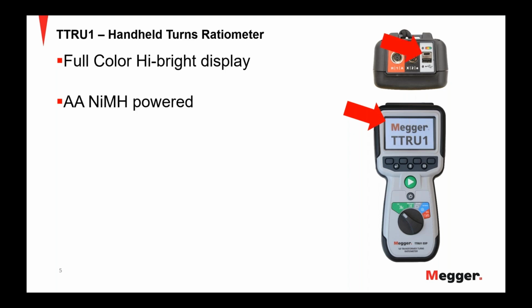It is a battery powered device, and AA batteries are nothing new, but what is new is the ability to charge the batteries using a USB-C cable. The USB-C cable is the same cable that you're using on your smartphones today, whether it is Samsung or Apple, because as most of us know, Apple is going to the standard USB-C type of cable. Thank you to the European Union. And with a full battery charge, you can test up to 1,000 turns ratio tests. So, whether you are in a parking lot testing a bunch of transformers or you're testing a few transformers a day, the TTRU1 will have the battery longevity to get you through that day's worth of testing.